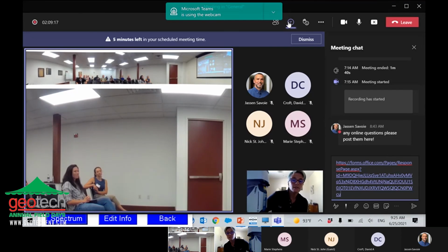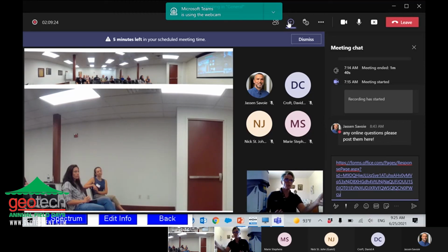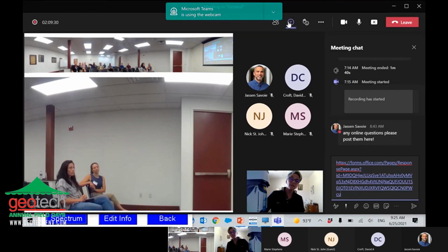Sure. So on a wall, that's why it's so important not to switch these. You can't shoot with an XRF that's calibrated for lead paint on a wall down on soil and expect to get any realistic results. I keep stressing that because I get that question. Even this week I had that question. Can we just shoot chips or on the ground and identify?